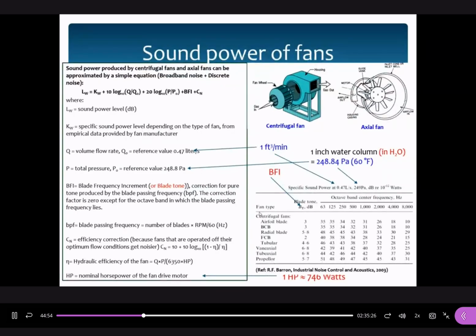For the blade passing frequency, it is referenced to the number of blades. In the example, we have 55 blades, as given in the question. The number of blades times RPM, the rotational speed, divided by 60, gives the frequency in Hertz. Remember this formula.